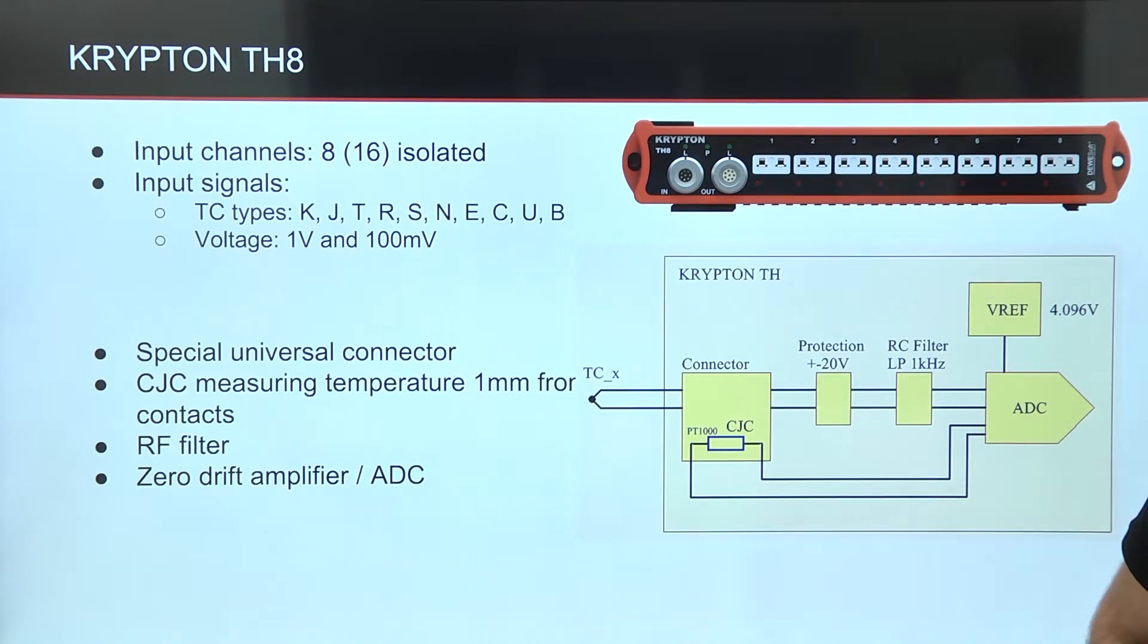It has eight channels designed like this on the block diagram. The connector is universal type, meaning you can connect any type of thermocouple cable. Modification of the connector is done in a way that the PT1000 for measuring the temperature of cold junction is just one millimeter from contacts. Measured voltage goes through protection circuit, RF filter, and to AD converter. Data from AD converter is read by microprocessor which then calculates temperature from measured data and sends it over EtherCAT bus.